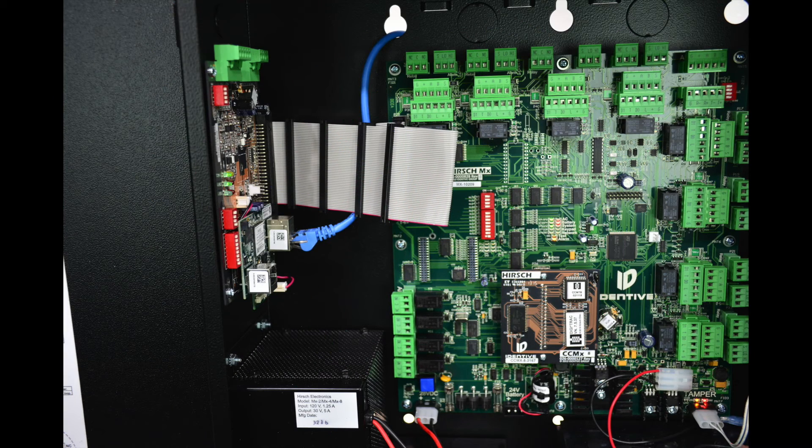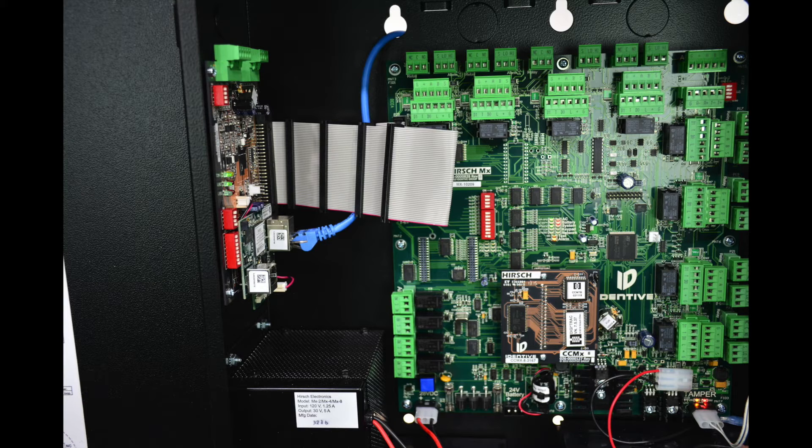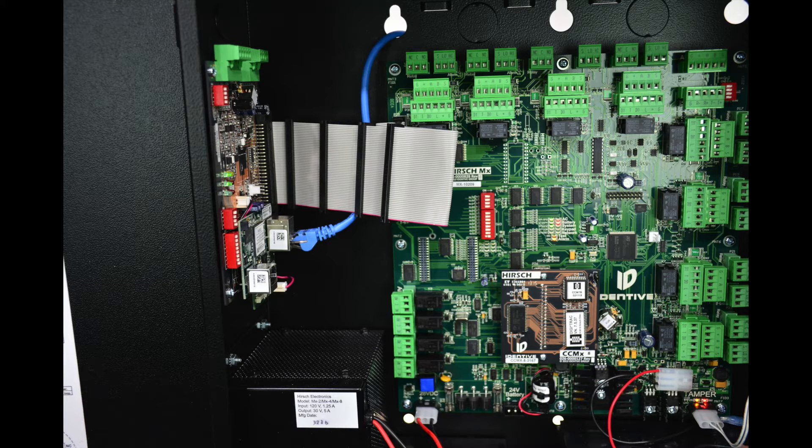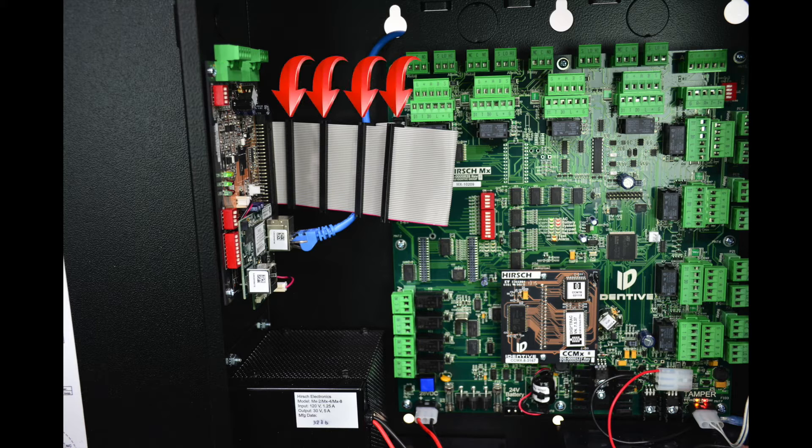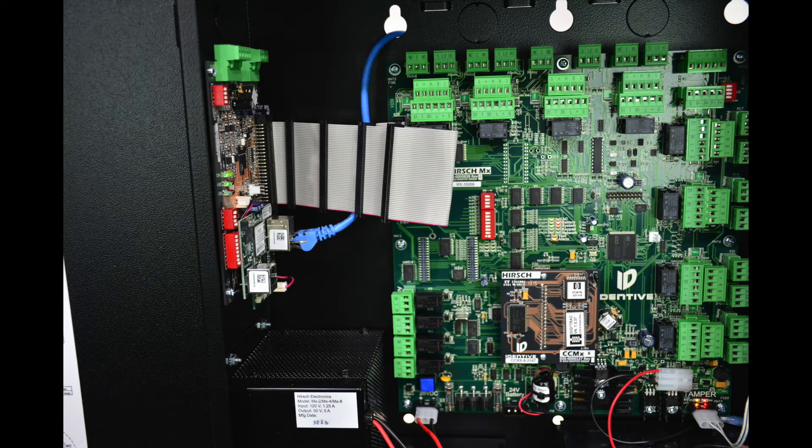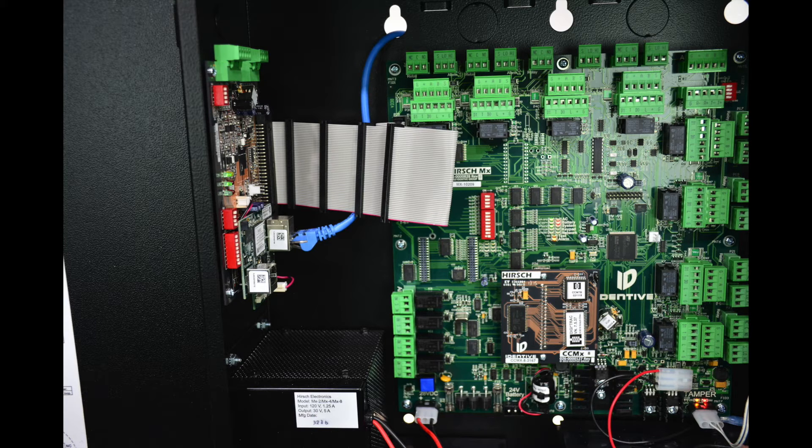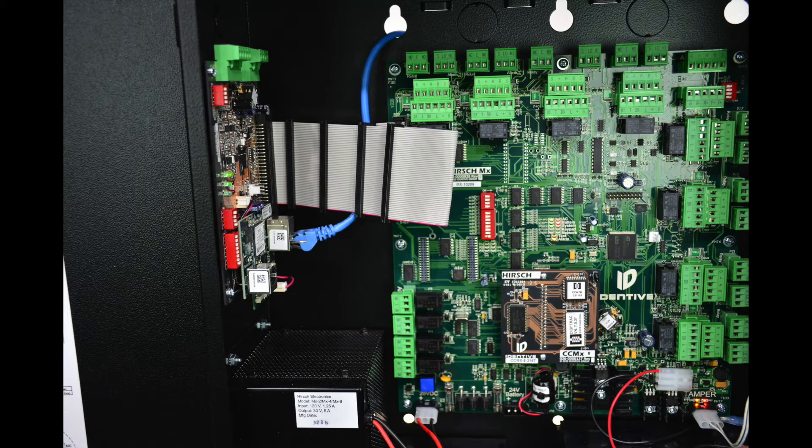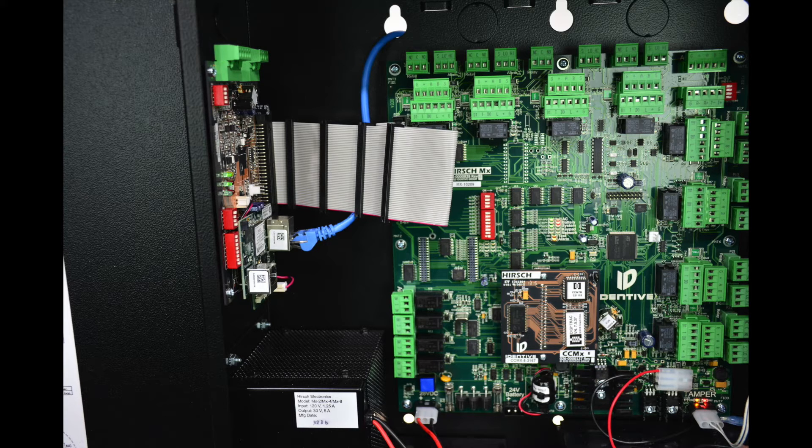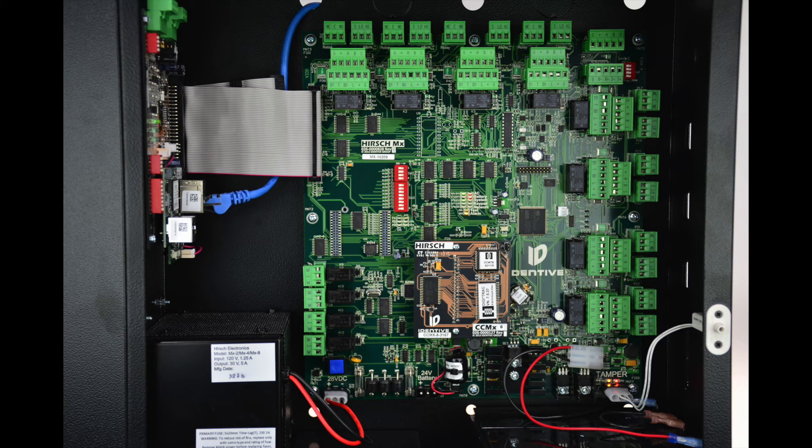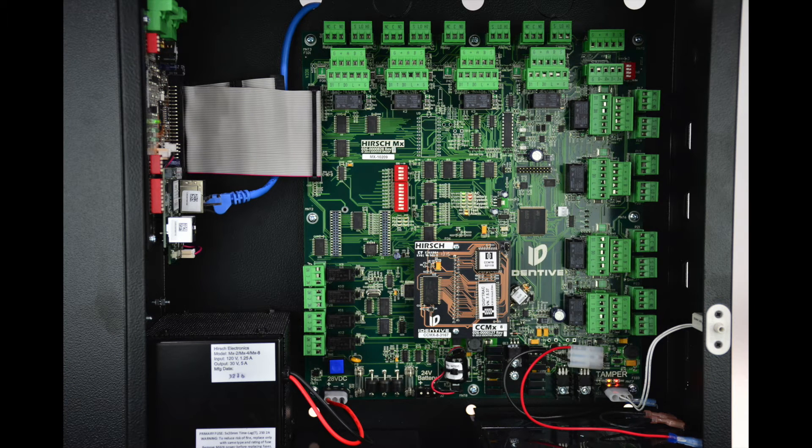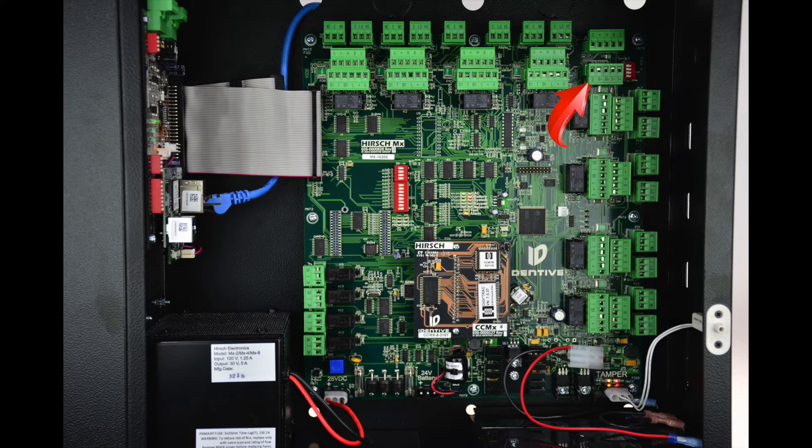Another feature of the MX is the capability to add expansion input and output boards inside the enclosure. Each MX can support up to four expansion boards, which attach to the ribbon cable that connects to the SNIB-3. Each of the expansion boards has either eight inputs or eight outputs, giving you the capability to add up to 32 ports of expansion inside of each MX. We can also daisy-chain up to 16 MX controllers together off a single Ethernet port, via RS-485 cabling.